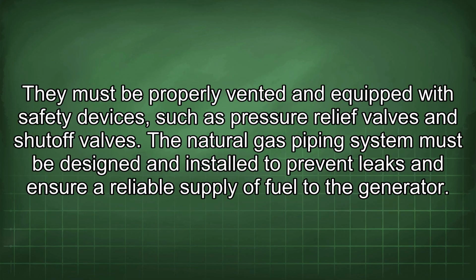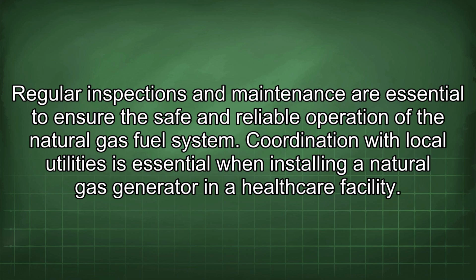They must be properly vented and equipped with safety devices, such as pressure relief valves and shut-off valves. The natural gas piping system must be designed and installed to prevent leaks and ensure a reliable supply of fuel to the generator. Regular inspections and maintenance are essential to ensure the safe and reliable operation of the natural gas fuel system. Coordination with local utilities is essential when installing a natural gas generator in a healthcare facility.